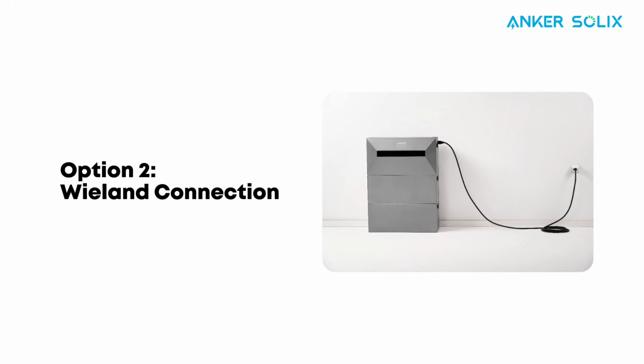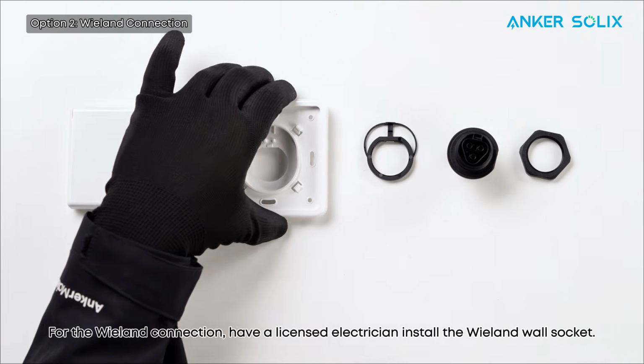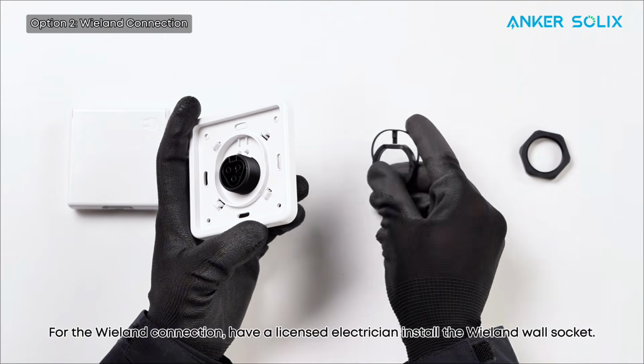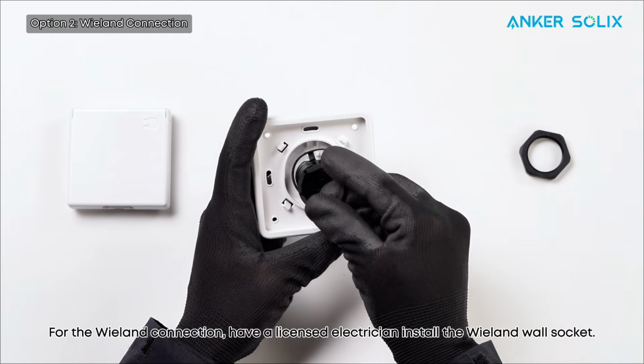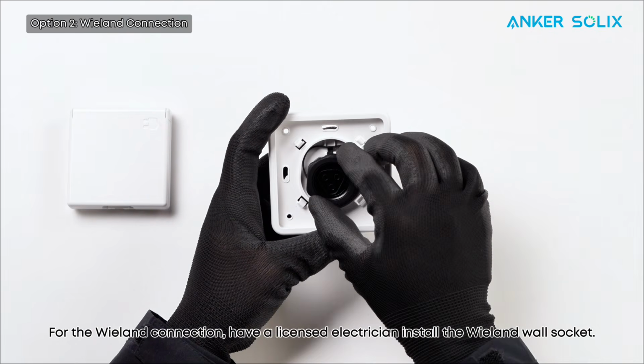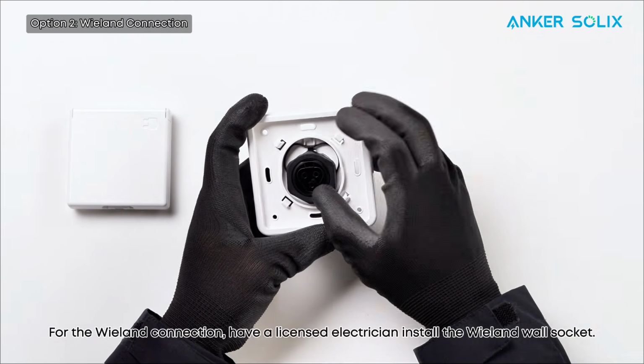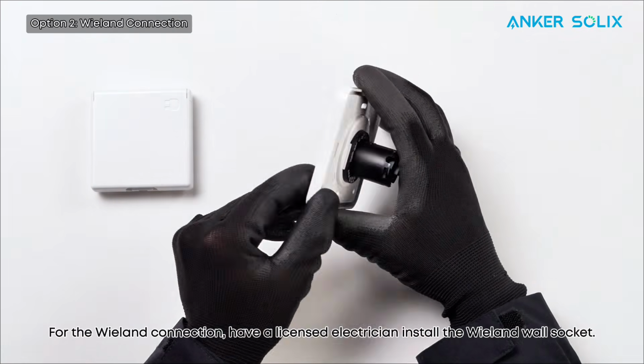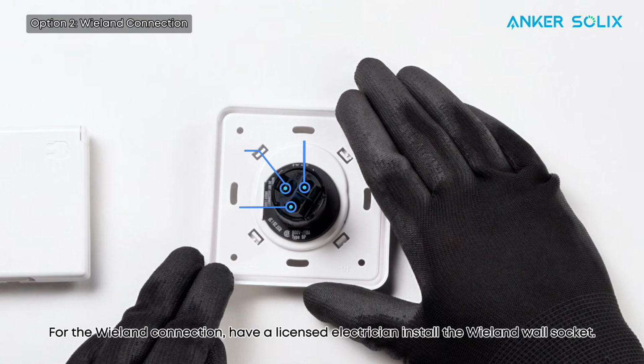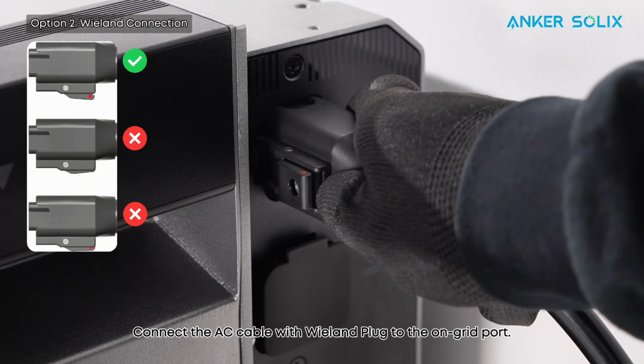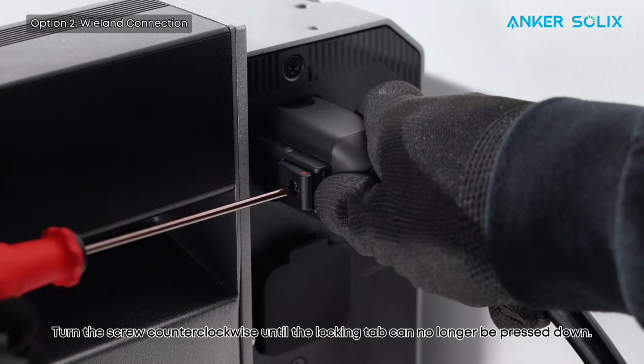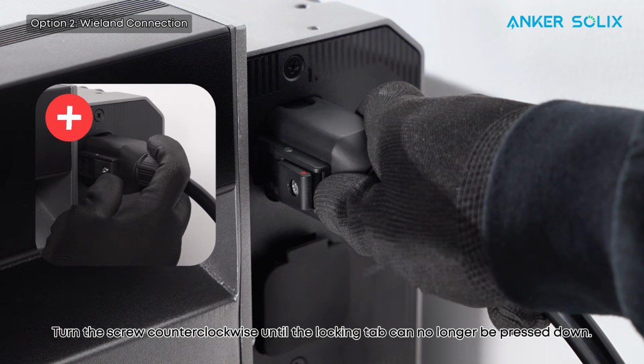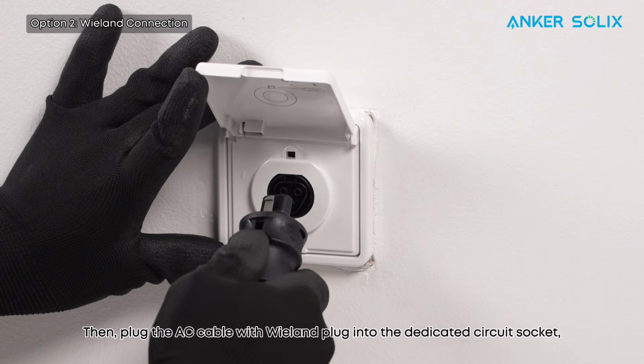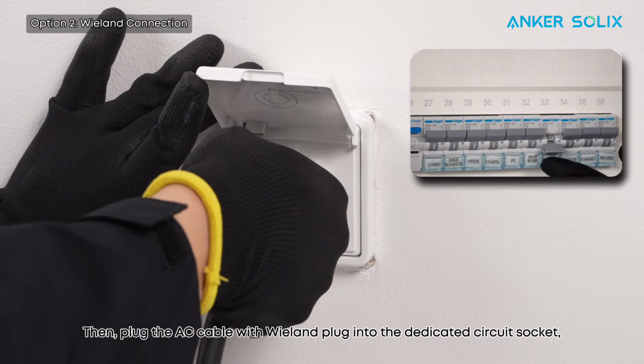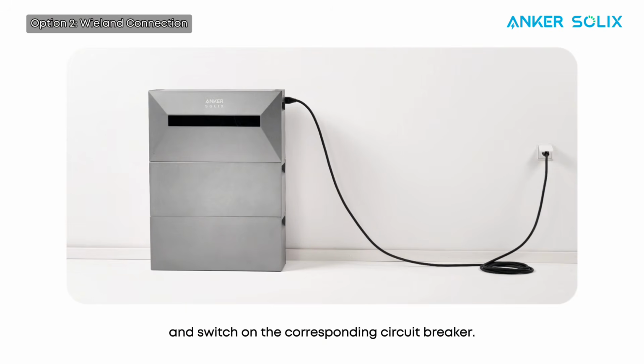Option 2. Wieland connection. For the Wieland connection, have a licensed electrician install the Wieland wall socket. Connect the AC cable with Wieland plug to the on-grid port. Turn the screw counterclockwise until the locking tab can no longer be pressed down. Then, plug the AC cable with Wieland plug into the dedicated circuit socket, and switch on the corresponding circuit breaker.